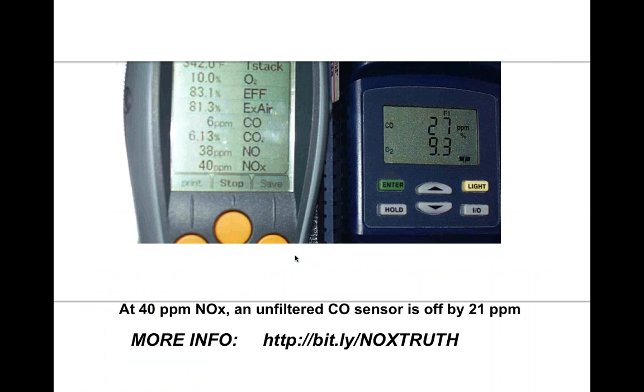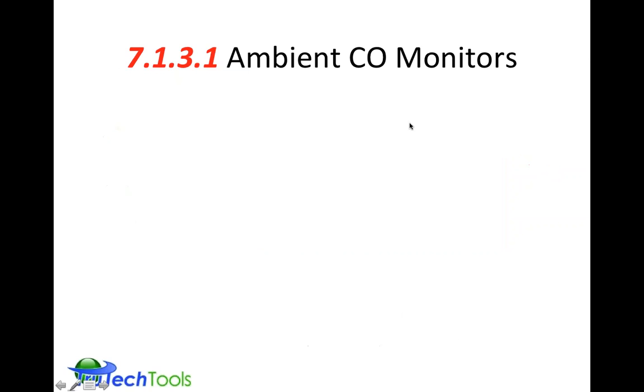So this was a test that was done where a combustion analyzer that has both a nitric oxide sensor as well as a nitric oxide filter was installed and measuring the same as a product that did not have a nitric oxide filter. So if you look at the reading here, you'll see 27 parts per million CO. If you look over here, you'll see only 6. The reason for the difference is the sensor in this device does not have a NOx filter in it, so it is not filtering out the NOx, and it's being added into the CO reading, additive to the CO reading. Over here you can see the NOx sensor says there's 38 parts per million of NOx in this flue gas stream. Now this meter does not even have a NOx sensor in it, so it doesn't know the difference.